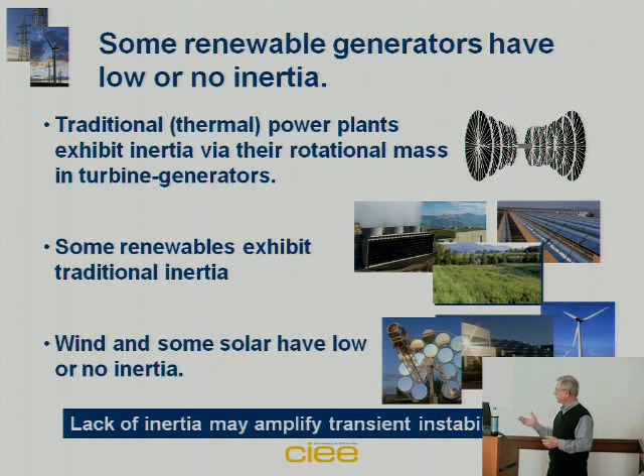There are also other issues. Yes, you can handle them with spinning reserve, but the whole WECC has to be able to model the load, and these technologies are changing those models. Just like residential air conditioners have dramatically changed load behavior—we have a research project helping develop new models for these air conditioner systems that cause voltage sag problems—we're predicting similar issues with rooftop photovoltaics affecting the load so the existing models don't work. And if you have wrong models, you do the wrong things. That's another issue on top of finding a way to get spinning reserve.